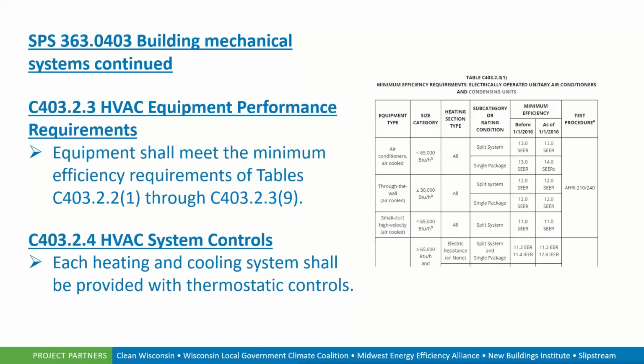There are efficiency requirements. These tables are rather extensive when you look at section 403.2.3. So they need to meet the heating efficiency requirements of tables 403.2.2(1) through (9). So it's a rather large section encompassing all types of heating and cooling equipment, making sure that we meet those categories, the equipment type, the size, and the efficiency as a requirement for the commercial energy conservation code. And as always, each heating and cooling system shall be provided with thermostatic controls.